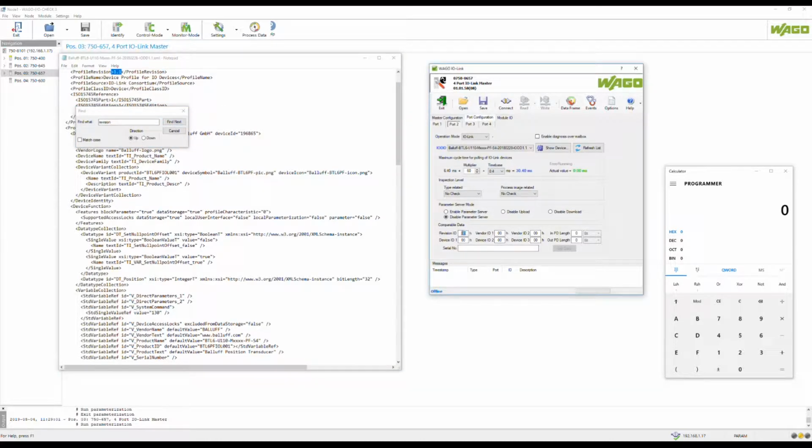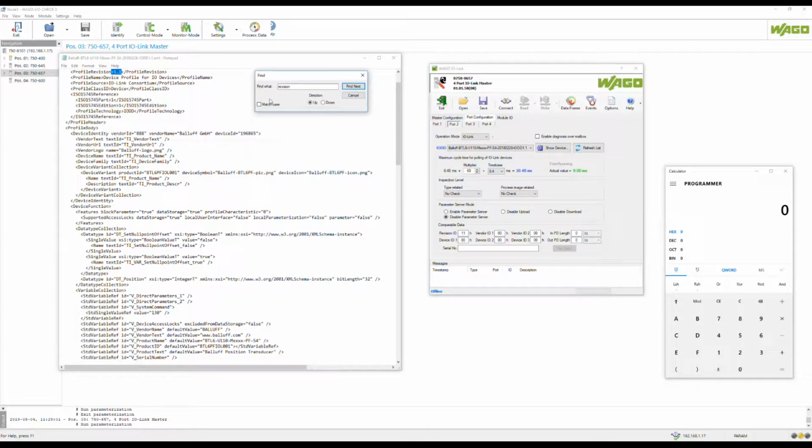So you're gonna enter 11 here. Again, the vendor, since it's Balluff, is the same 888 that we did for the stack light. So 888, if you remember that, if you copy here, put a decimal and paste, is 0378. So first part, vendor ID is 03, second part is 78.